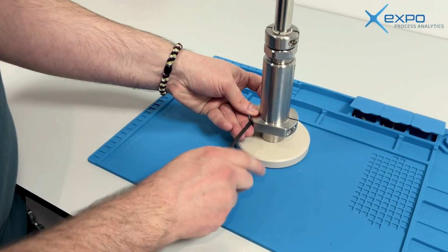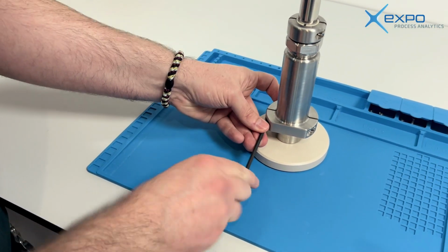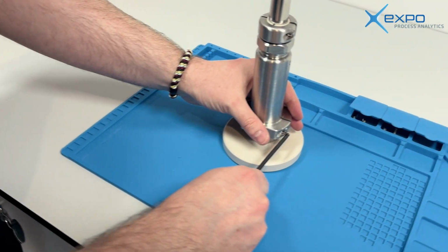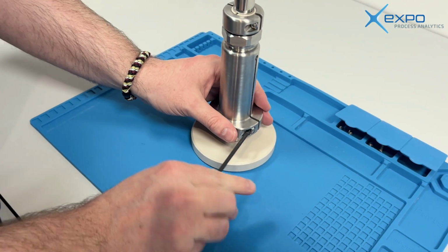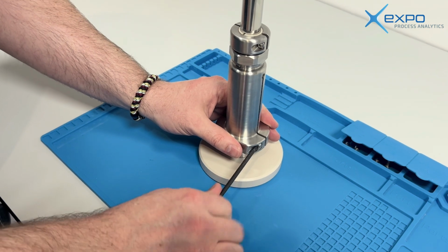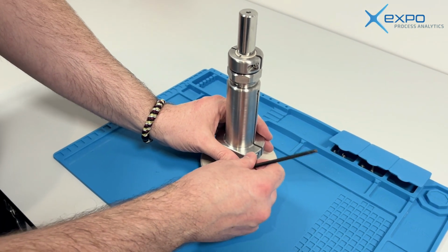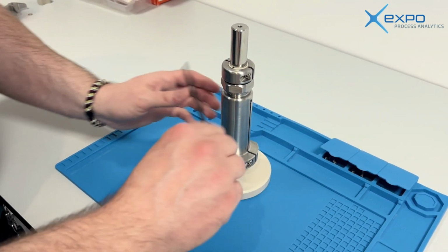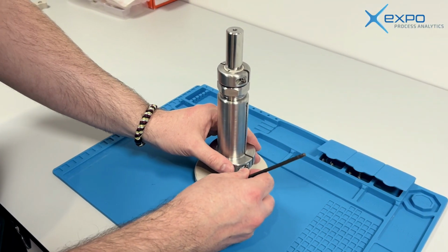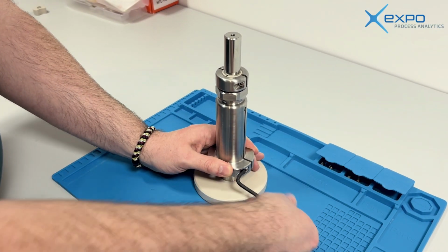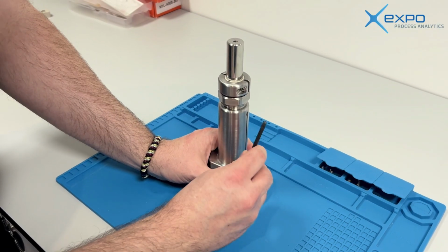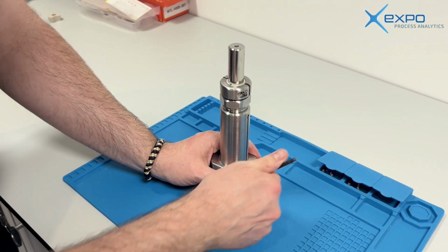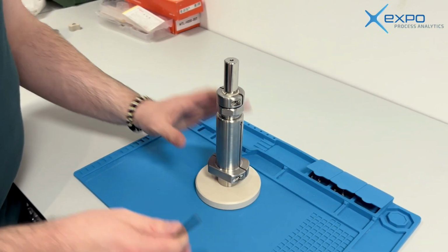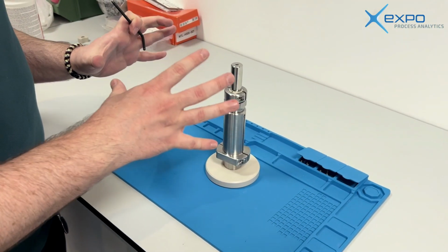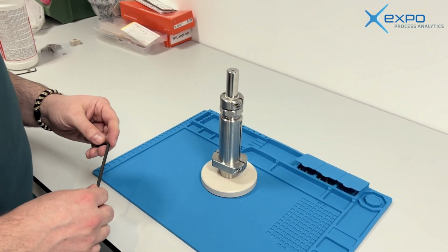points, two clamped screws, one there and one there, and same thing as before. What you want to do is tighten these evenly and incrementally, so in sort of 0.2 or maybe 0.3 Newton meter increments back and forth, so that it's clamped evenly. Okay, so shorten that there, but that is then the setting tool height set.